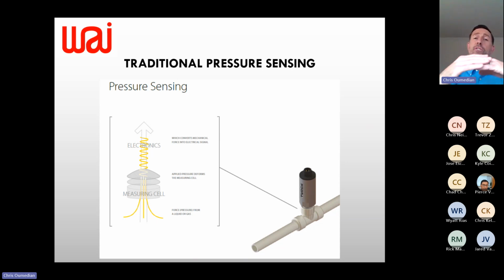As the pressure goes up, that device flexes, the strain gauge stretches out, and then you've got some interpreting electronics on the back end that take the output from the strain gauge and turn that into something usable, which might be a switch point, a transistor switch point controlling a relay. Most popular would be an analog output, 0 to 10 volt, or more popular, 4 to 20 milliamp for process automation. And we've built some intelligence into these, as with all the other sensors.